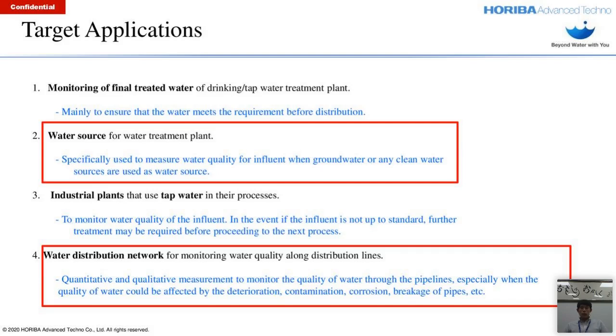Okay, the TW100 can be used for various applications. For today, I'd like to focus on mainly two applications. The first application is number 2, the water source for water treatment plant, and number 4, water distribution network for monitoring water quality along distribution lines. For target application number 2, the TW100 is used to measure the water quality of the influent to determine if the influent meets the requirement for the purification process. If the influent does not meet the requirement, pre-treatment will have to be performed. And in most countries, pH, temperature, and conductivity of the groundwater and clean waters are usually measured as influent as well.